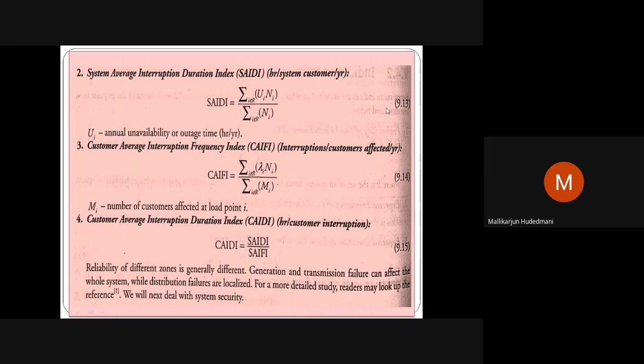At each load point, so many consumers are connected and each has outage. Annual unavailability is known to us in hours per year. This load point cannot supply the load to the consumers. So each load point has U i, the unavailability, in hours per year. Multiply with N i for all the load points and sum them, which becomes the total system hours of unavailability, divided by the total system customers, the summation of N i with i from 1 to R. When I take the ratio, it becomes hours per system customer per year. So the disconnection experienced by each customer in a year is given by this parameter.